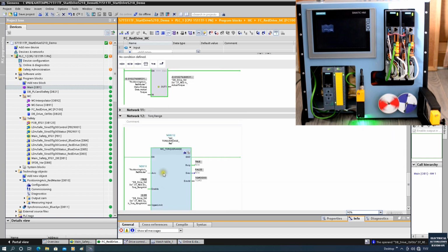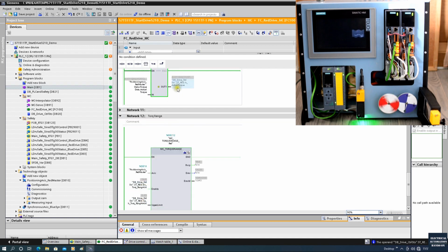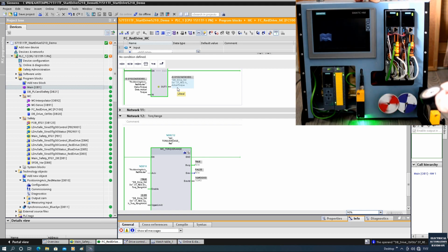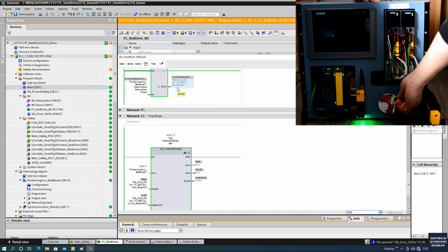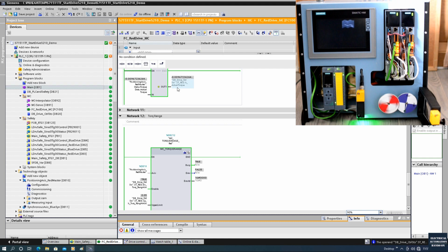And now we can see while it's running in the backward direction, this torque feedback is showing negative. And let's see, once I apply the load, this value should show negative 0.03 here. Okay, so now I will apply. Apply, no fault, it just jams there. Release, free run, no flying. Apply. So we will see we get this negative 0.03. Release. Okay, this is the negative.